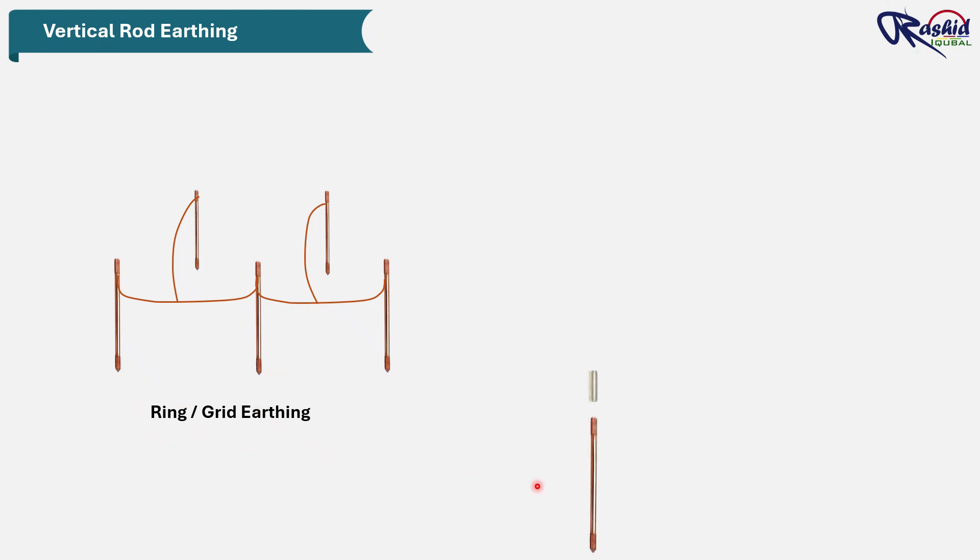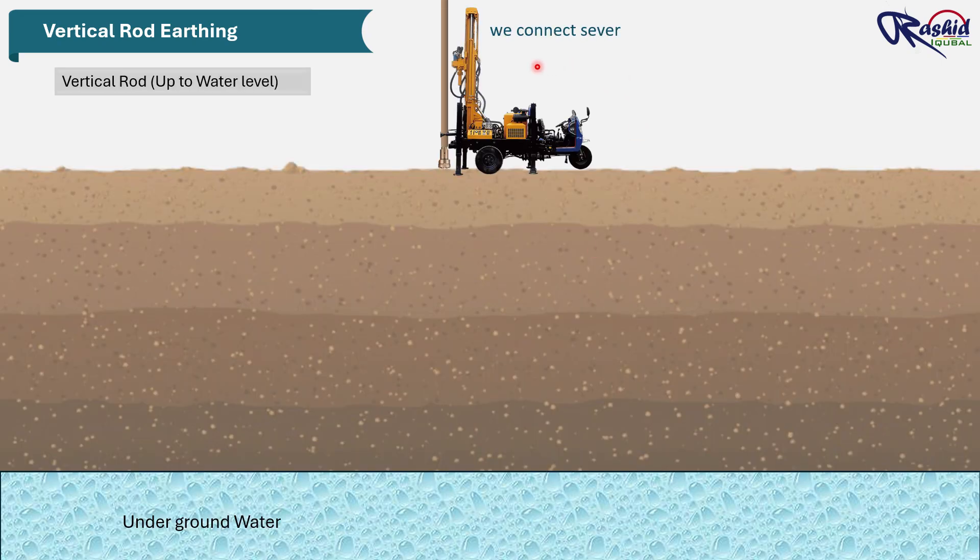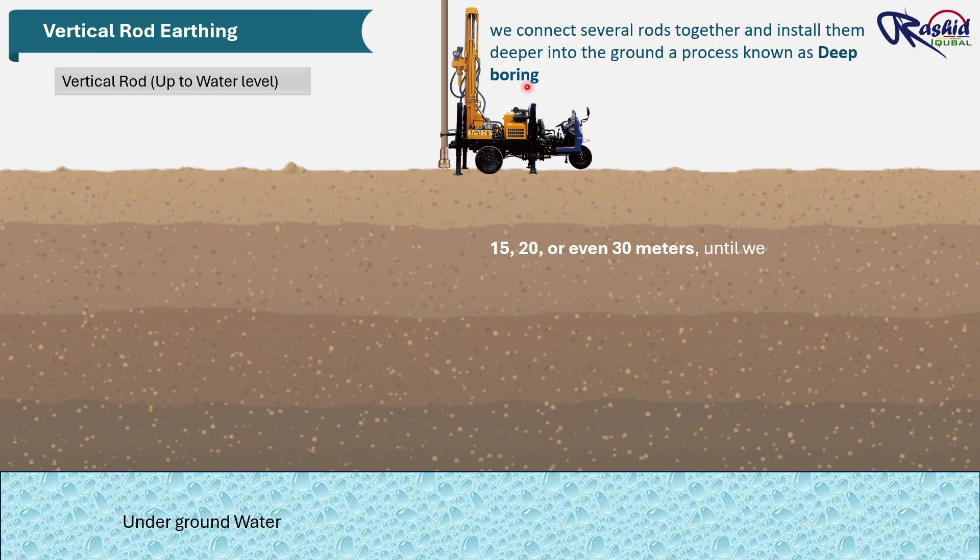Install multiple rods in parallel forming a ring or grid earthing system, which I already explained earlier. And the second method: drive longer rods deeper into the moist or more conductive soil layers such as clay or near the water level. In desert or hilly regions, especially in some Middle Eastern countries, the soil is extremely dry and the water table is very deep. Because of this, a normal 3 meter earth rod cannot achieve low resistance. So we connect several rods together and install them deeper into the ground, a process known as deep boring. In such cases, we use deep boring where the rod is installed much deeper, sometimes 15, 20, or even 30 meter or 40 meter, until we reach moist soil or water level.